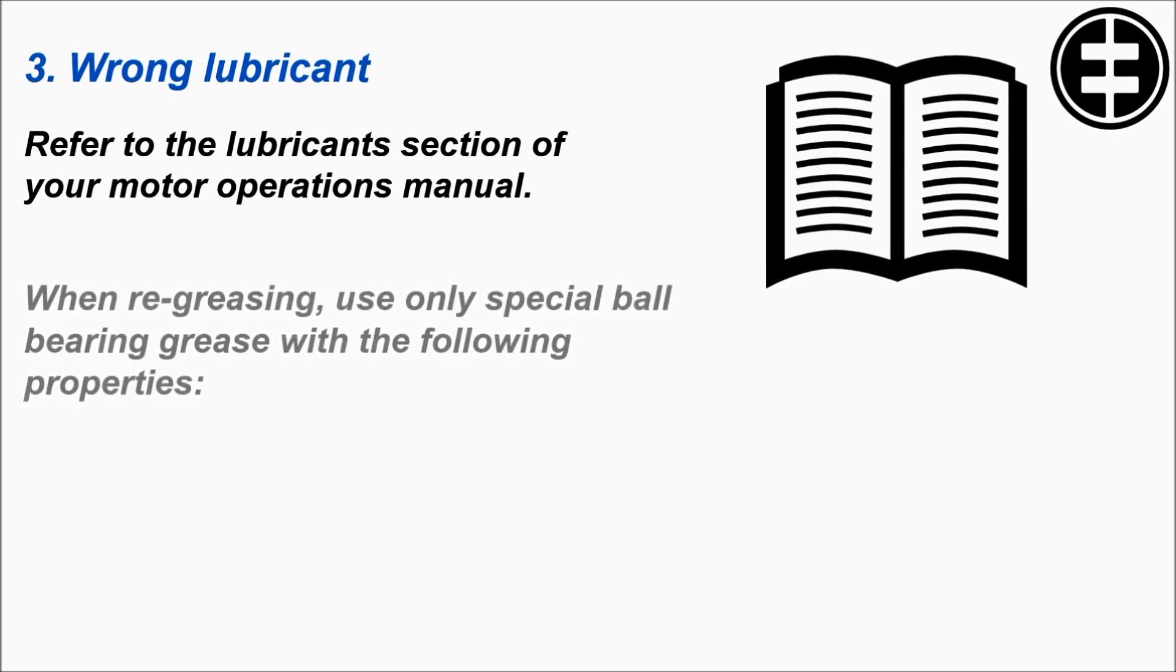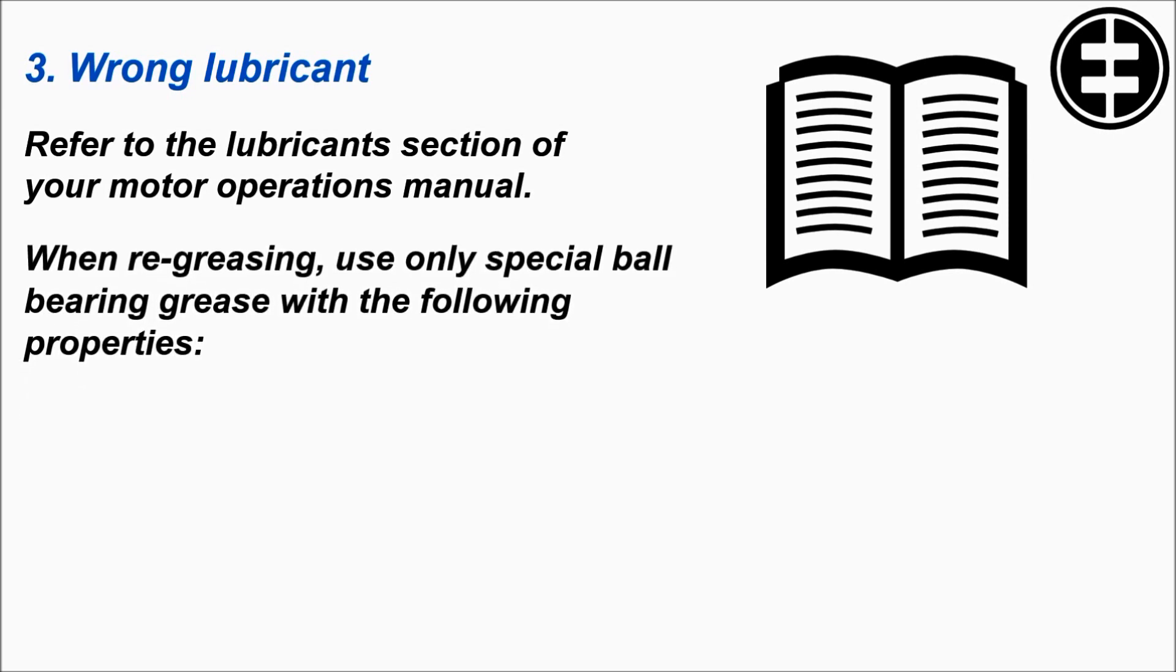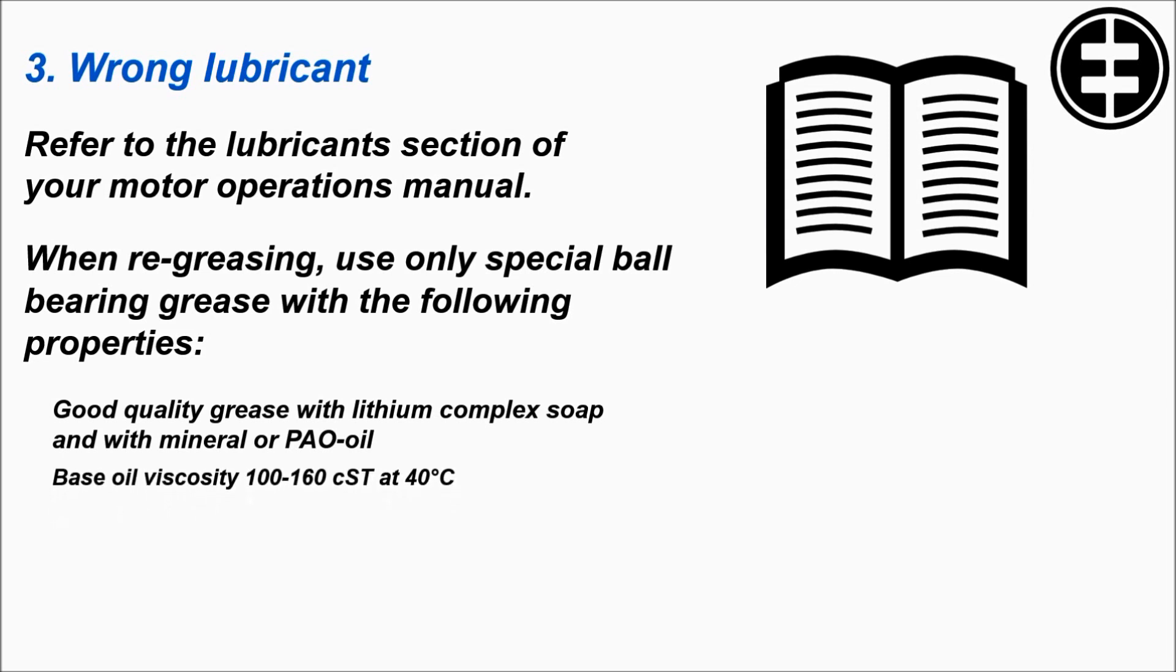When re-greasing, use only special ball bearing grease with the following properties: Good quality grease with lithium complex soap and mineral or PAO oil base. Oil viscosity 100 to 160 cSt at 40 degrees Celsius. Consistency NLGI grade 1.5 to grade 3. Temperature range minus 30 degrees Celsius to 120 degrees Celsius.